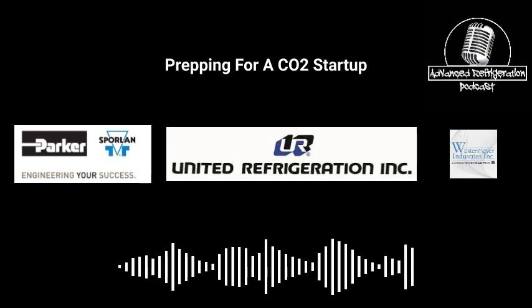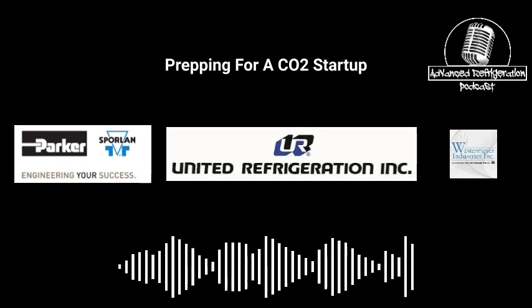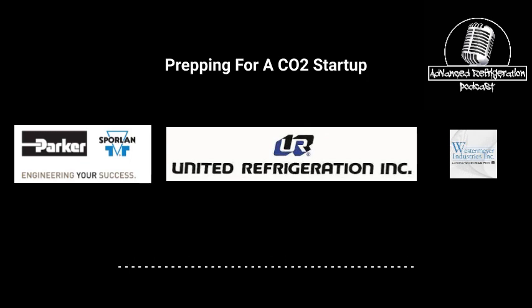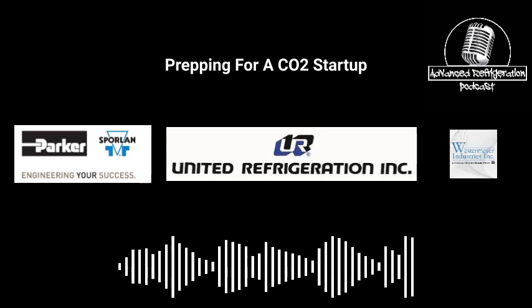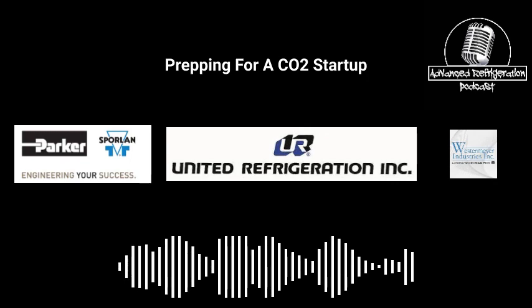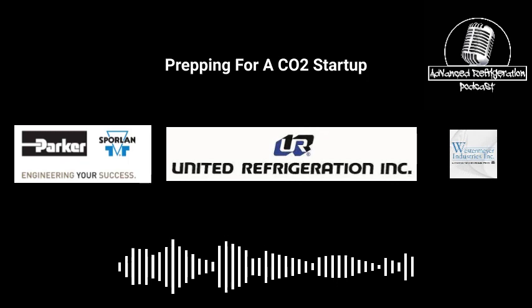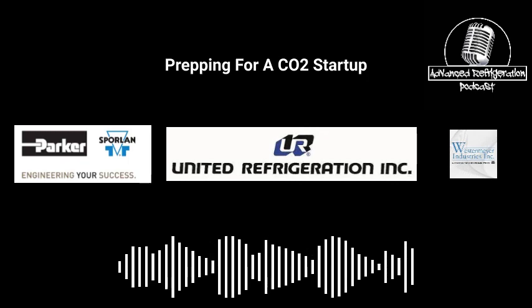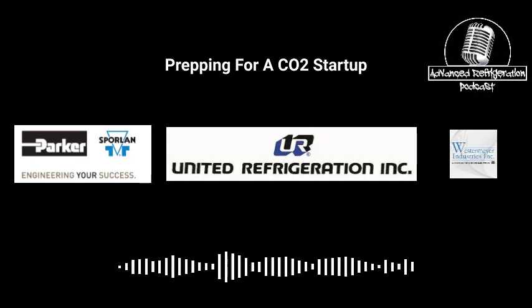And it's also going through the cases. So if you have any liquid flood back, it's going through cases that are 80 degrees probably. So flashing that stuff off right away. Get it all flashed off, then get it charged up, and then start up cases slowly. I usually will go a couple cases at a time. If it's loops, I'll turn on the first loop and go a couple cases at a time, just watching it, making sure we don't have any flood back and all the systems look good, and then we'll fire up a couple more cases and a couple more.